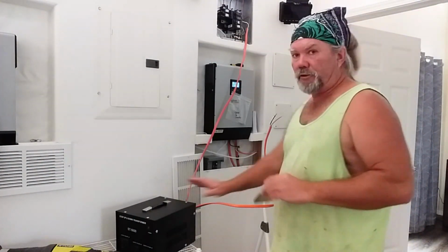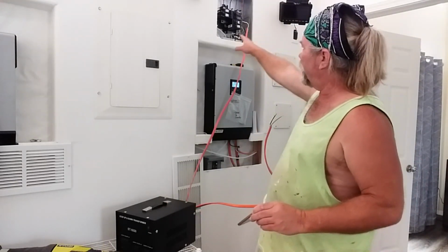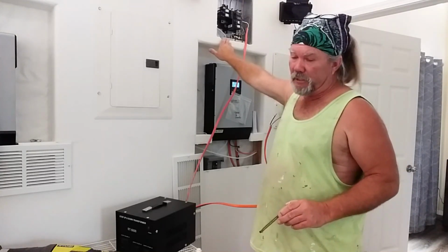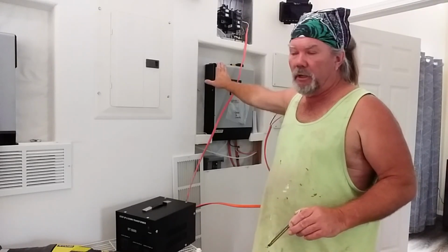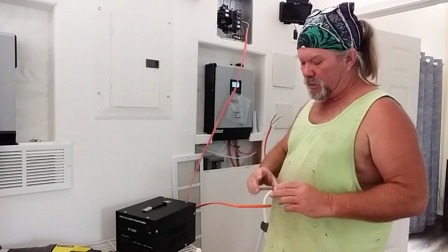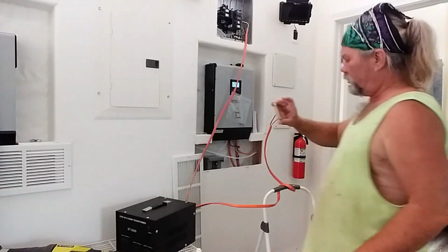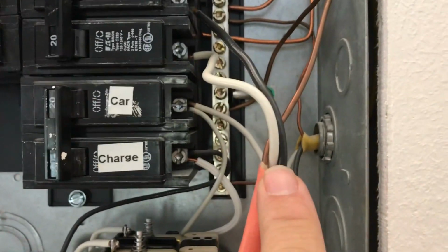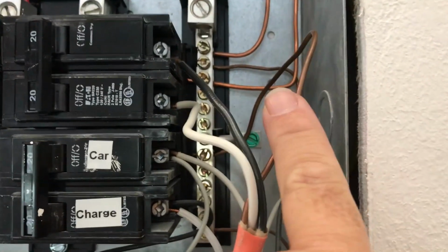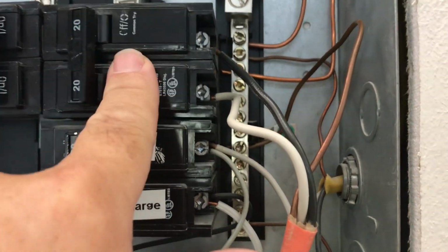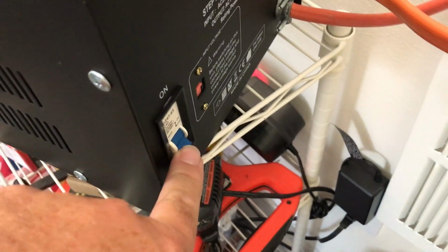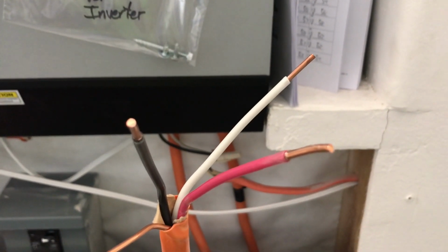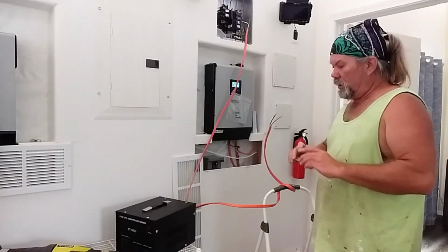Okay. I've got the transformer brought into the house and I've run it up to this panel. This panel only has 220. It does not have 110 in it because it runs directly off of this PIP inverter, and that only runs the water heater and the car charger. So I'm going to switch over to this phone camera here and show that these 2 wires, you can see this is the NM-B 2 conductor. I've got the ground going to the ground, and then the white and the black going to this breaker, and it is on. And then the switch on the back of this transformer is off. And then I've got the output with just bare wires up here, and we're going to look at the voltage on this shortly.